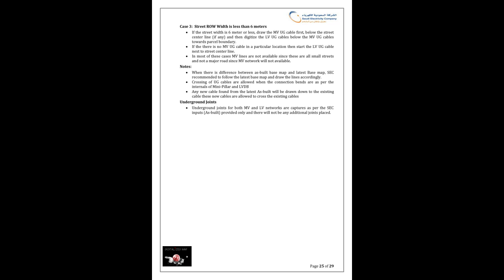Notes: when there is a difference between the as-built base map and the latest base map, SEC recommended to follow the latest base map and draw the lines accordingly. Crossing of UG cables is allowed when the connection bends are as per the internals of the mini pillar and LVDB. Any new cable found from the latest as-built will be drawn down to the existing cable. These new cables are allowed to cross the existing cables. Underground joints. Underground joints for both MV and LV networks are captured as per the SEC inputs, as-built, provided only, and there will not be any additional joints placed.